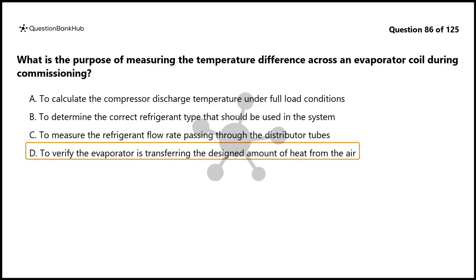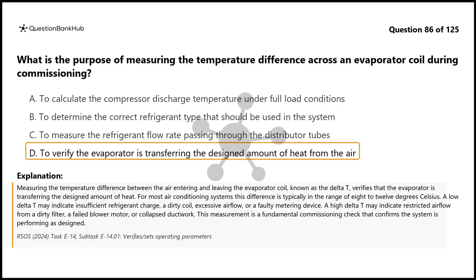The correct answer is D. Measuring the temperature difference between the air entering and leaving the evaporator coil, known as the delta T, verifies that the evaporator is transferring the designed amount of heat. For most air conditioning systems, this difference is typically in the range of 8 to 12 degrees Celsius. A low delta T may indicate insufficient refrigerant charge, a dirty coil, excessive airflow, or a faulty metering device. A high delta T may indicate restricted airflow from a dirty filter, a failed blower motor, or collapsed ductwork. This measurement is a fundamental commissioning check that confirms the system is performing as designed.